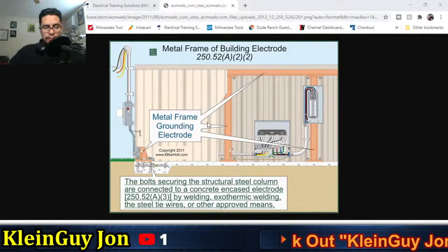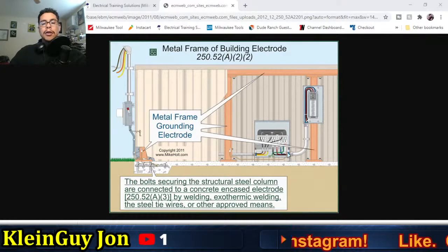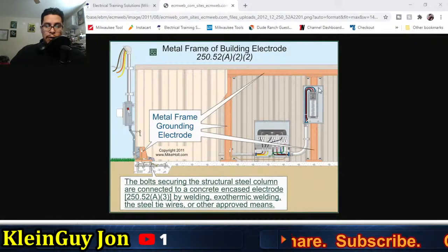Okay. What's next? So yeah, you've got that. If you are bonding, let's say a transformer, you need to bond the XO terminal to the structural steel. And your system bonding jumper also has to be bonded to the XO, because you want an effective ground fault current path if there were to be a fault here in the panel. A ground fault: you want the electrons to go through the metal, the EMT or the rigid pipe, from the supply, through the system bonding jumper and back into the XO, back to the source. You want that to happen.